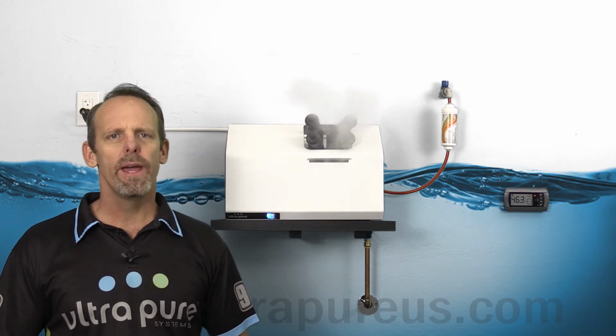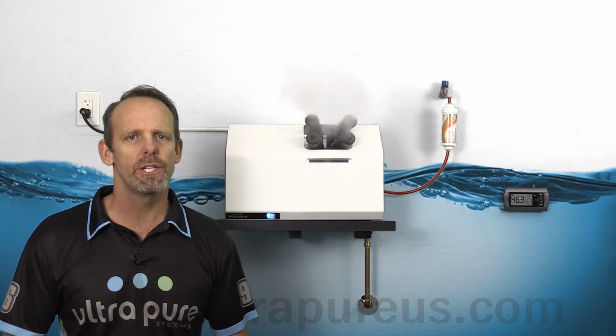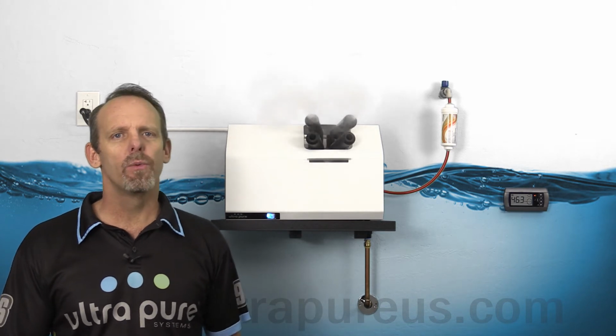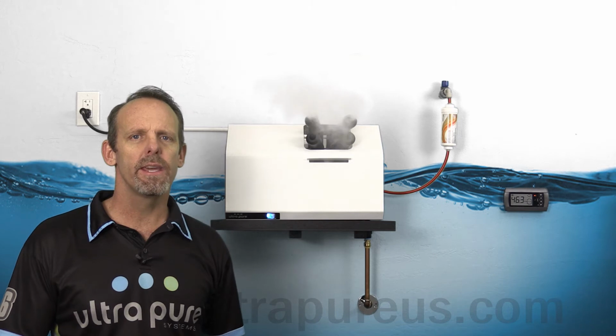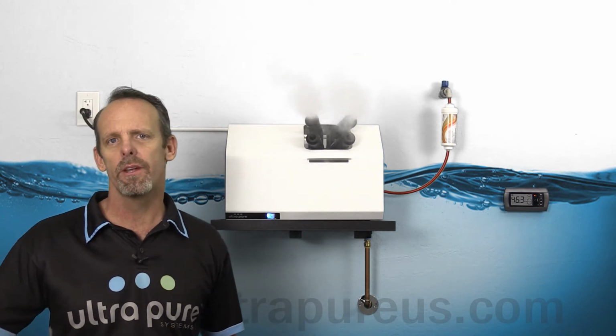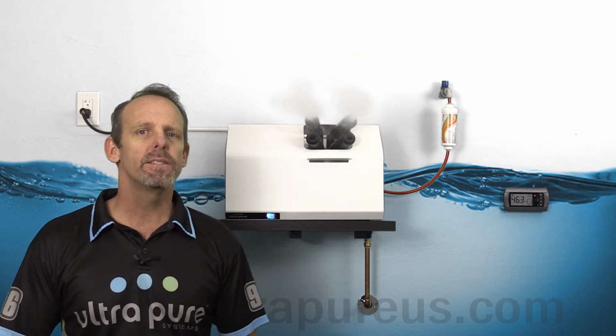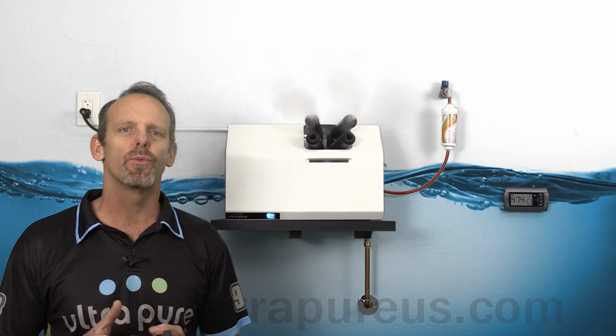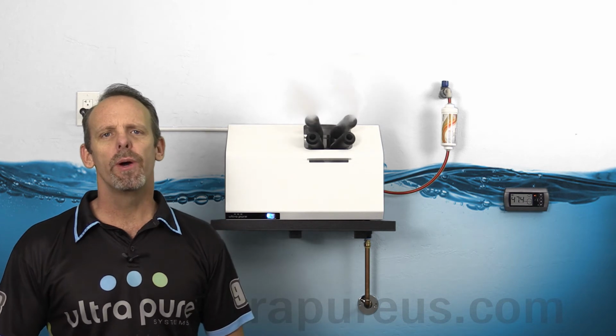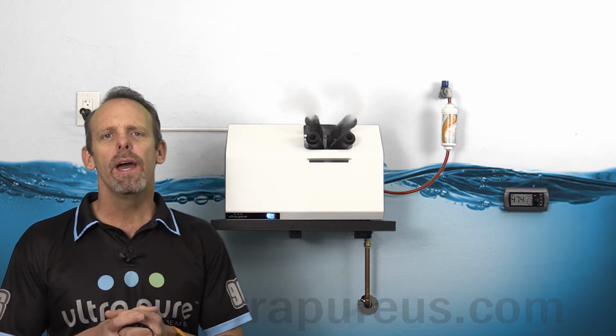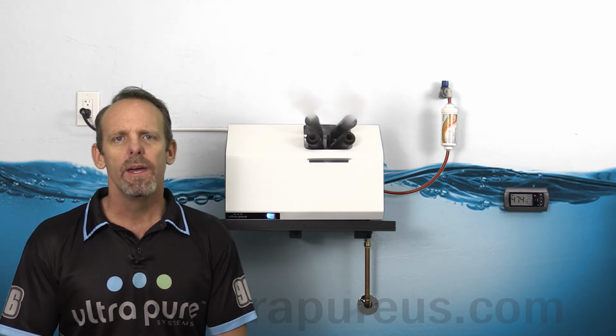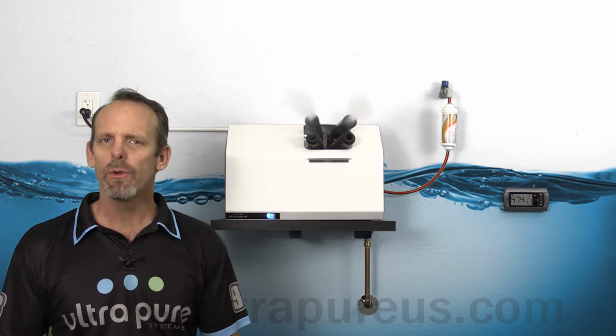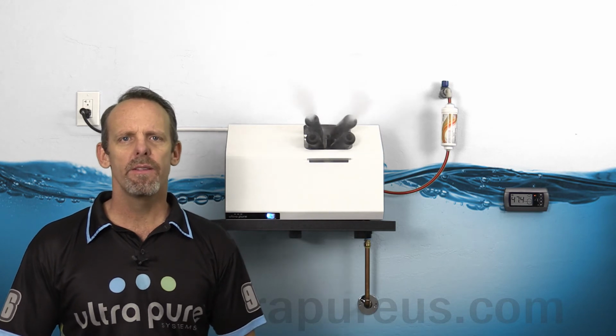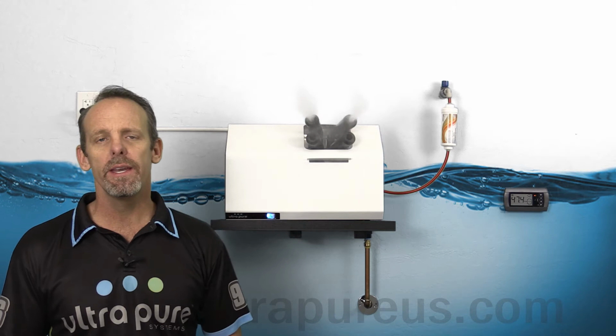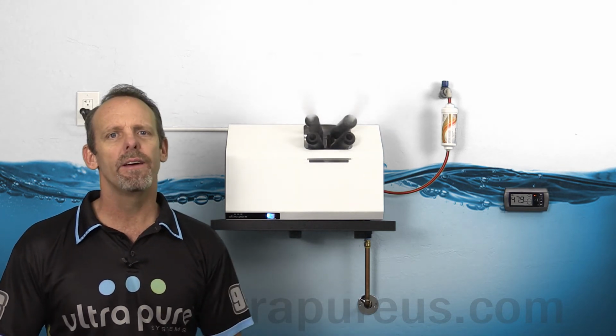Dew point control is such a great way to control a space, because it takes out the equation of temperature, which is often higher in one place than another and affects relative humidity. When you look at relative humidity and think it's low, but an instrument on the other end of the room reads higher, it could just be because temperature is skewing the RH — RH is relative to temperature. Dew point, on the other hand, looks at grains of moisture — how much moisture the air can hold at any given time — and shows you that as a number. It's a great way to go; I always encourage it. There are charts out there that convert a given temperature and humidity for you, so you can dial in your humidifier to that percentage or temperature. It works really well.